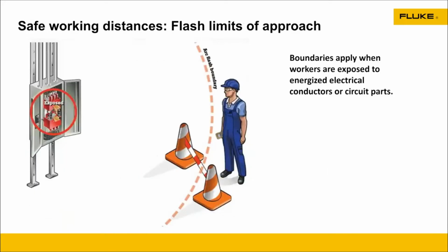So talking about that, if you've got some type of exposed electrical outlet, some distribution panel that you're working on, there are boundaries built into the NFPA of where you need to be. The farthest distance away is the arc flash boundary. We would set that up based on the potential energy of that distribution panel. What does that look like? Where they necessarily wouldn't need to have the full PPE on to walk around that. We actually set that boundary up.